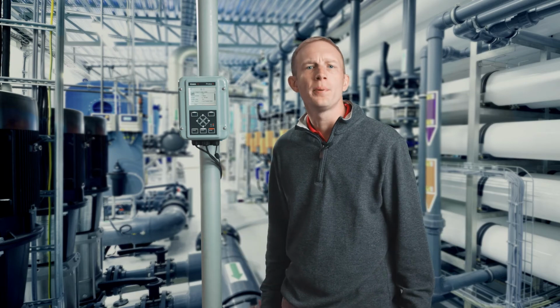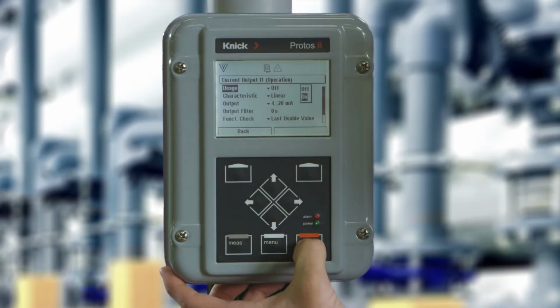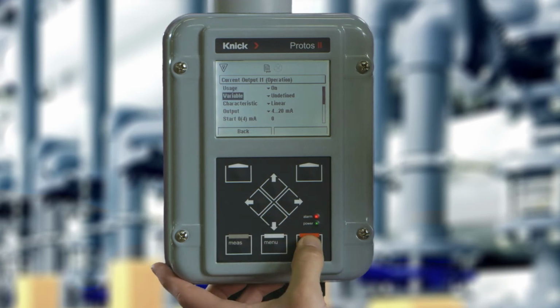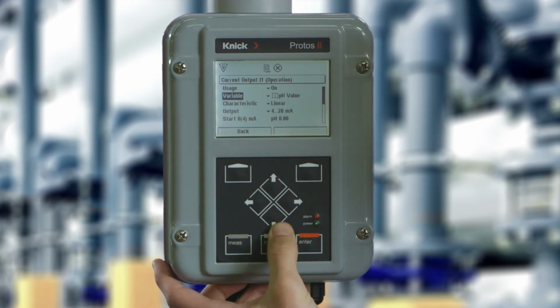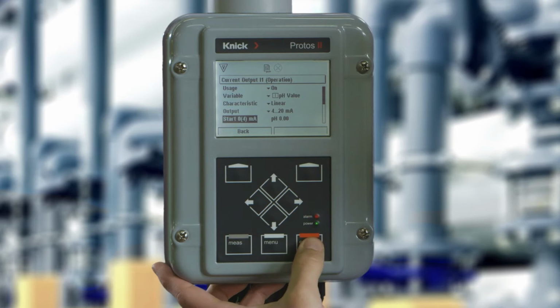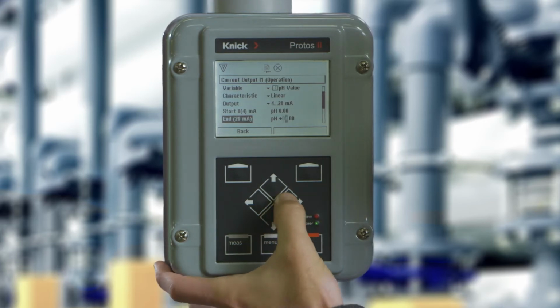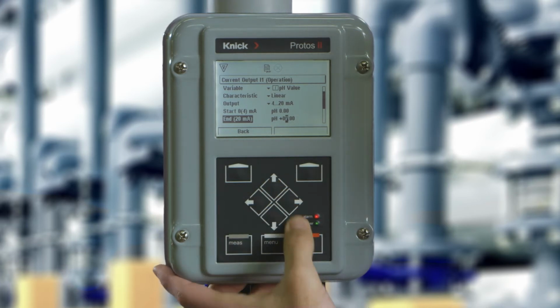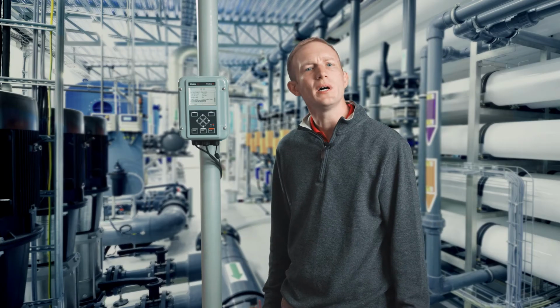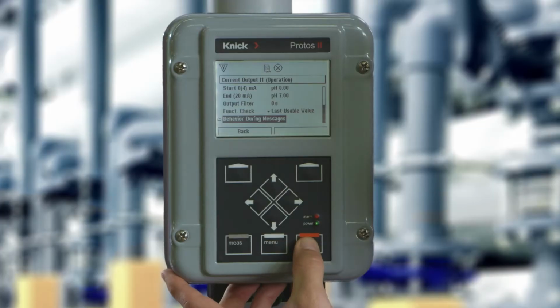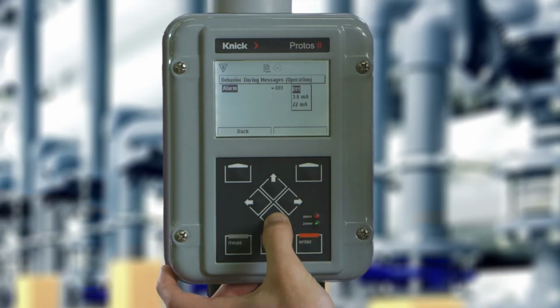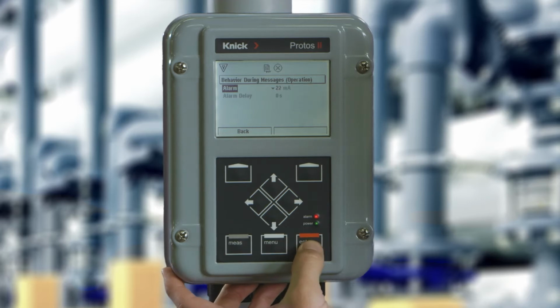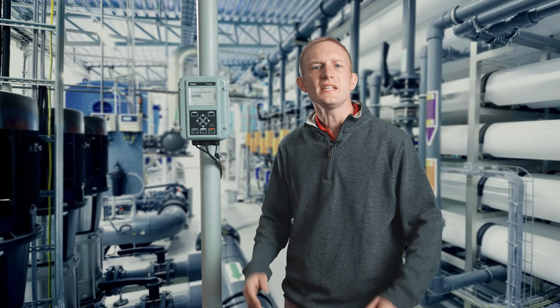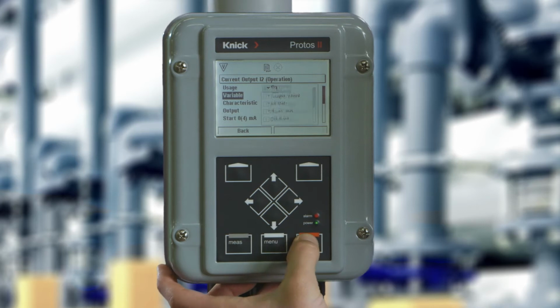We will turn on output 1 and configure it for a pH value from 0 to 7 pH. Lastly, we can define the milliamp output of the device when in alarm mode for either 3.6 milliamp or 22 milliamp. Let's continue and configure output 2 for conductivity from 0 to 600 microsiemens.